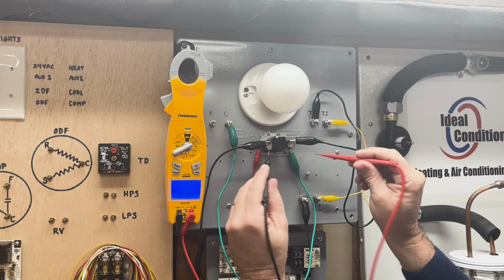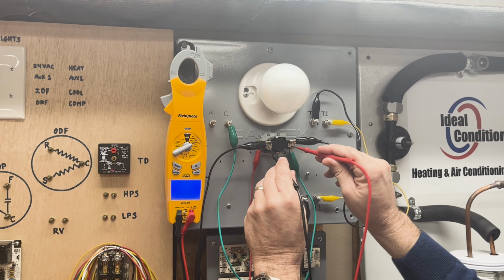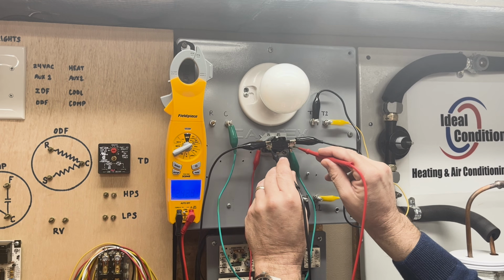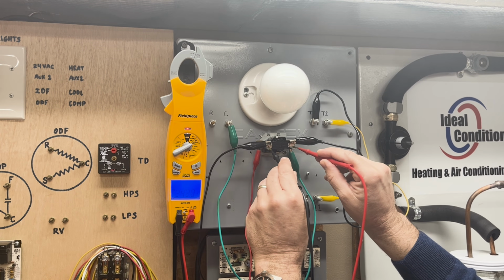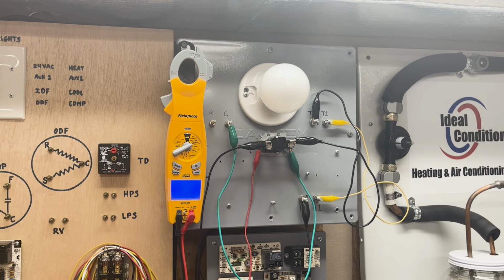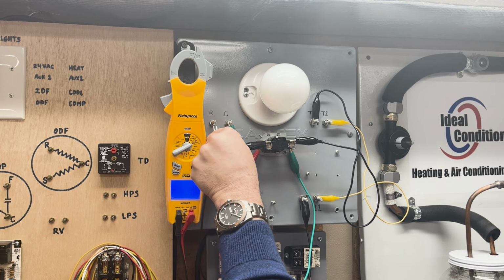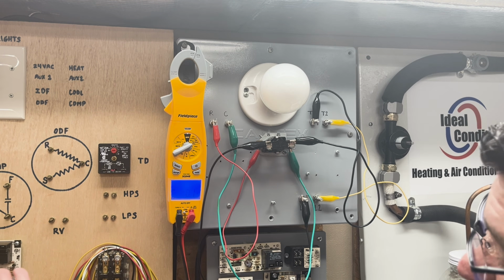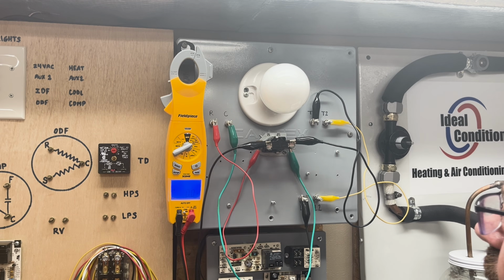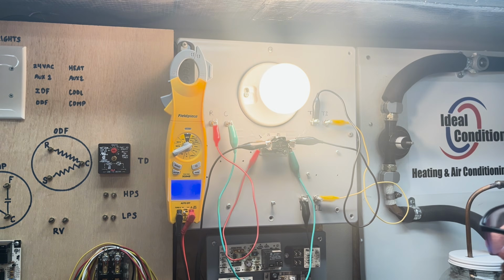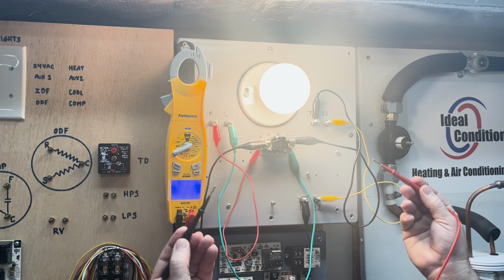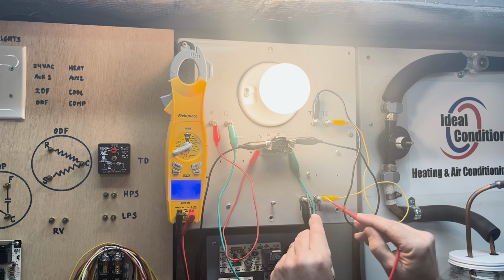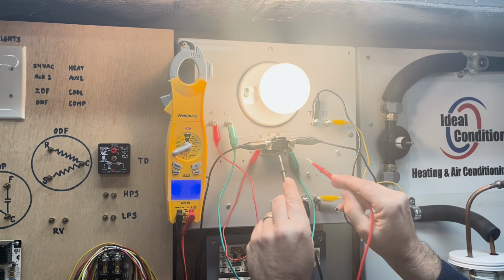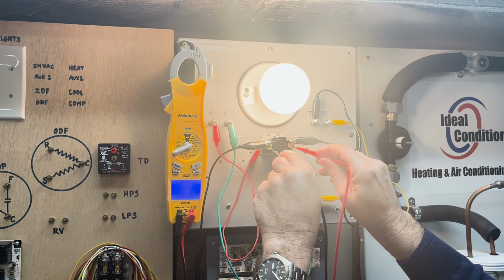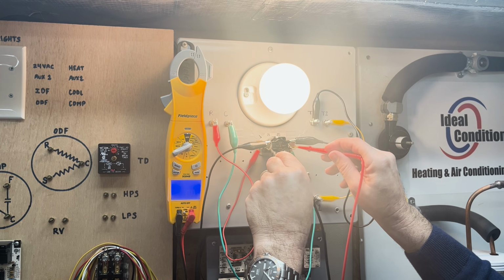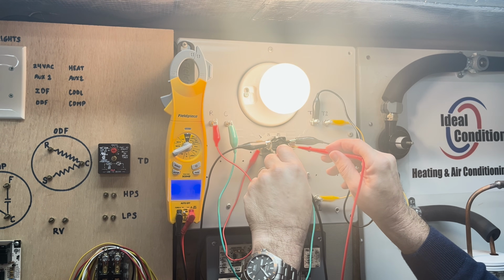is we'll measure across the points. And if you notice, I have a measurement of L1 plus L2. So I know the relay is open because I'm reading 243 volts of electricity. Now, if you notice, when we apply 24 volts, we're going to wait about 7 seconds, I think. The relay should energize. There we go. That's about 7 seconds. At least it feels like it. Now, if we wanted to see what the power supply is, down here we read our 242. Up here, we read our 242. But if we look across here, we read 0 because it's the same leg of power. We can't read a difference on L1 to L1 because it's still L1.